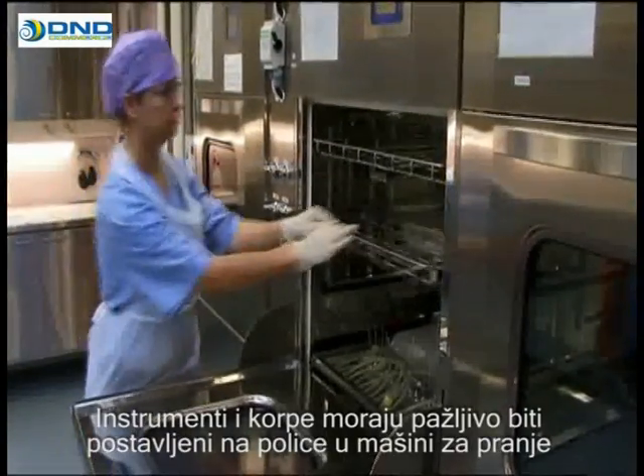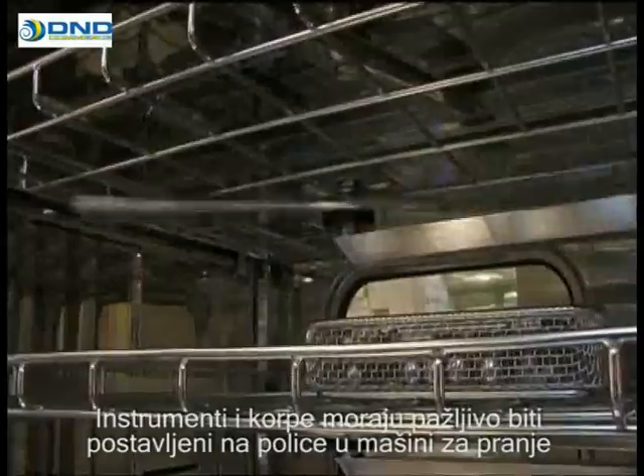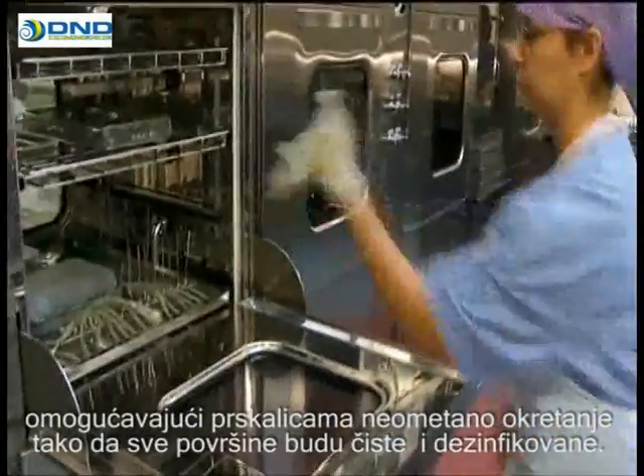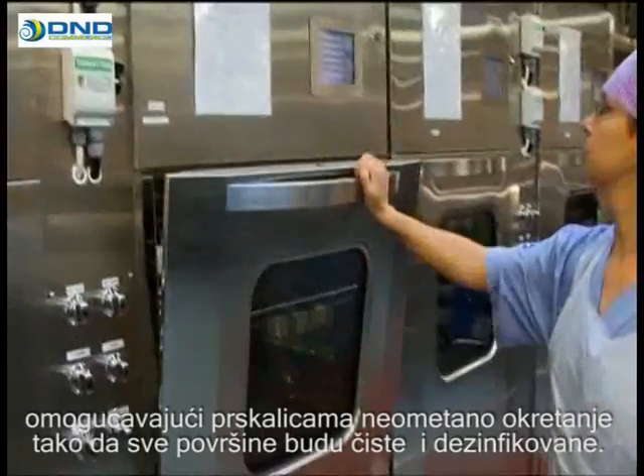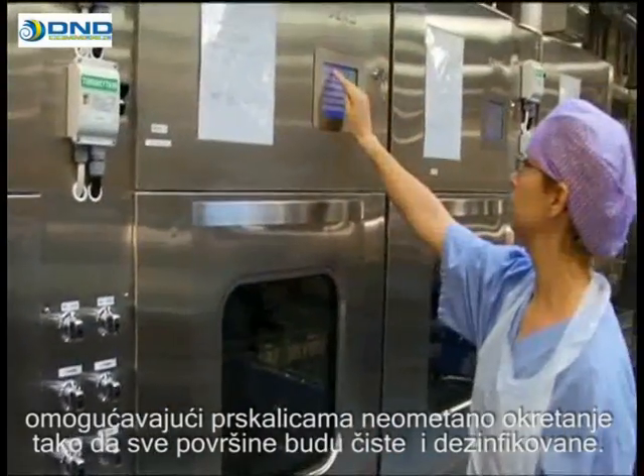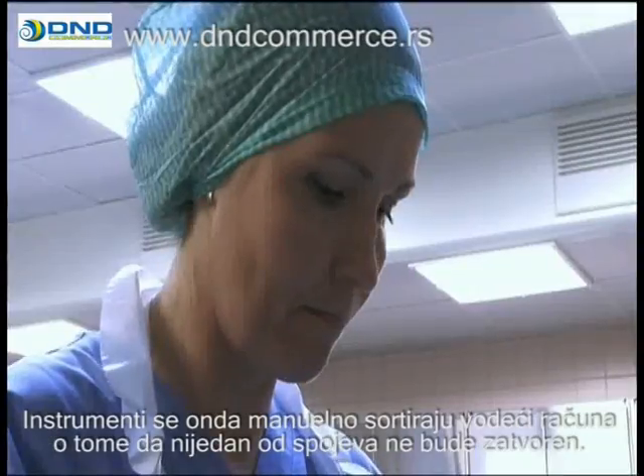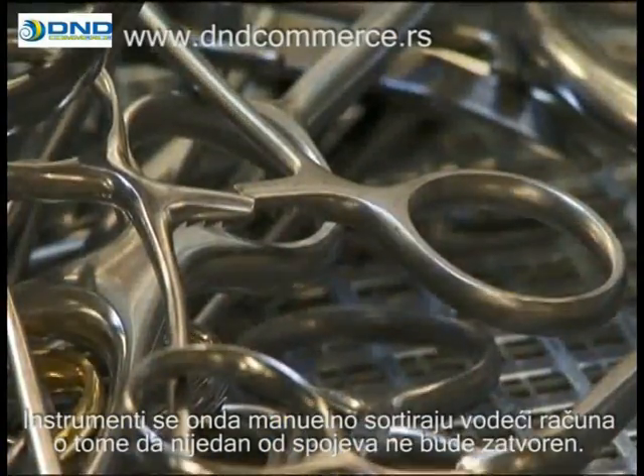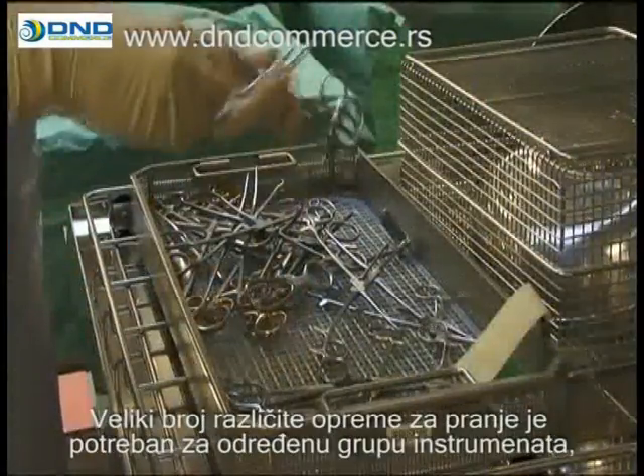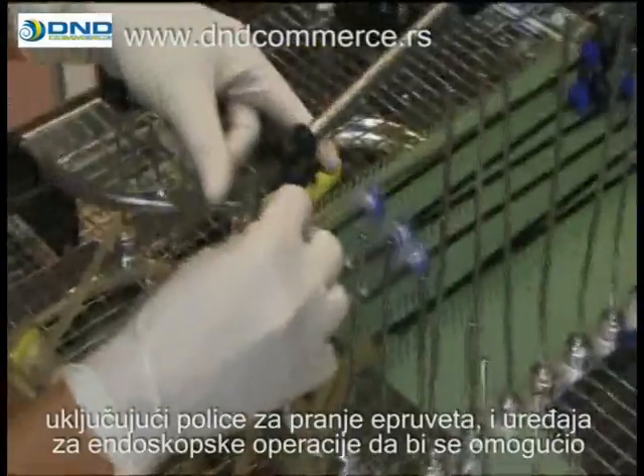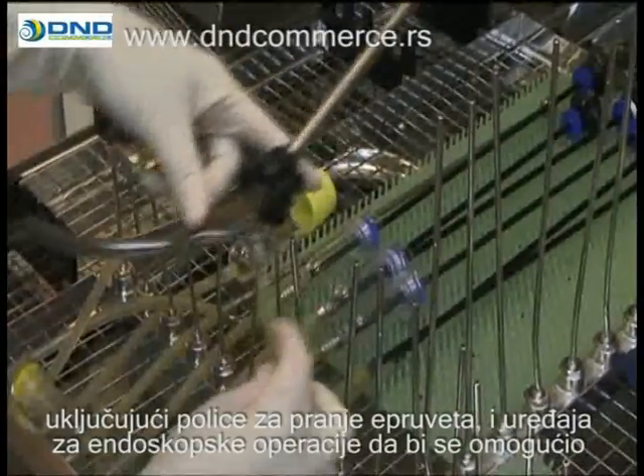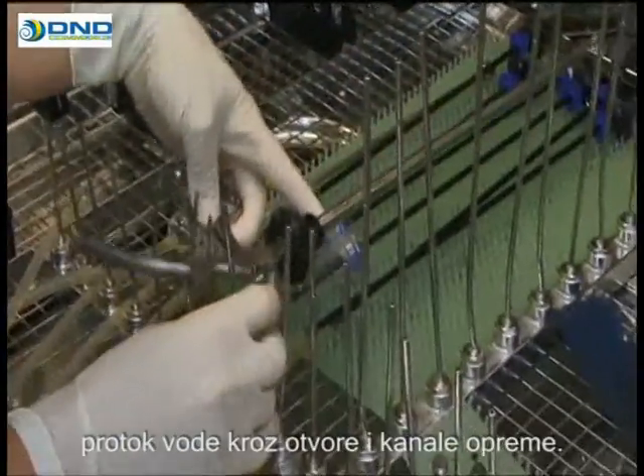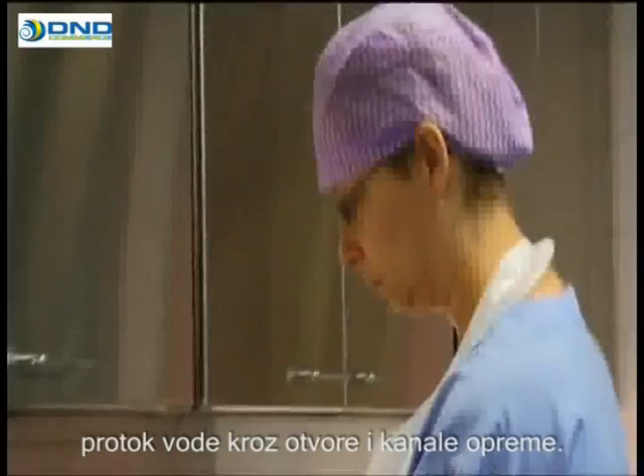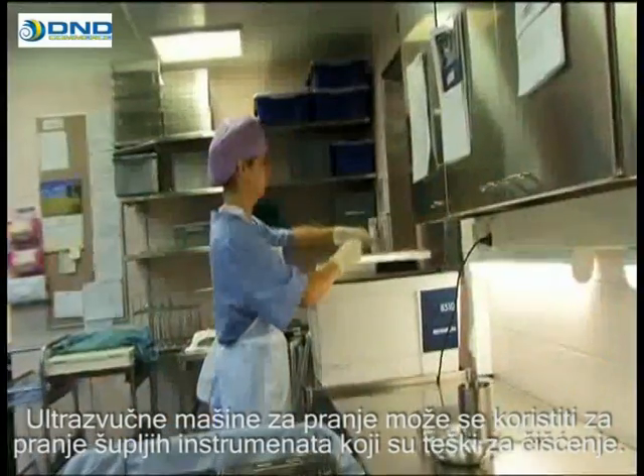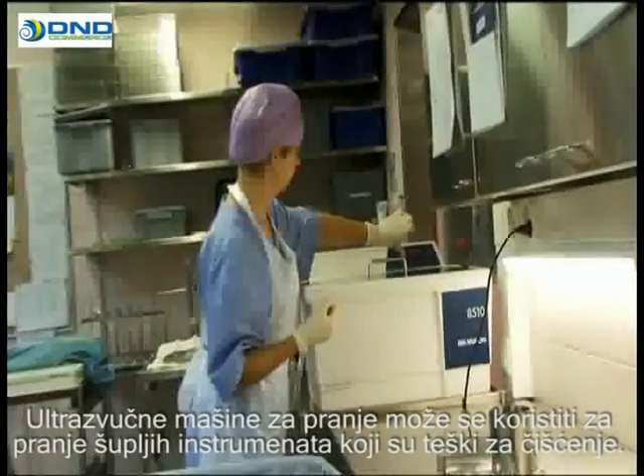Instruments and baskets must be carefully placed on the washing shelves, allowing the spray nozzle's full reach throughout the load and the chamber so that all surfaces are cleaned and disinfected. The instruments are then sorted manually, making sure that none of the joints are closed. A variety of different washing accessories is needed for certain instrument groups, including wash racks for tubes and endoscopic surgery instruments, enabling efficient flow of water through the channels and cavities of the equipment. Ultrasound washers may be used to wash difficult-to-clean hollow instruments.